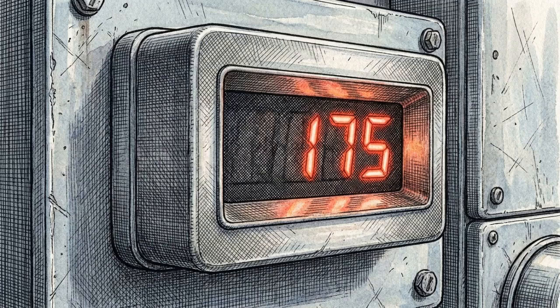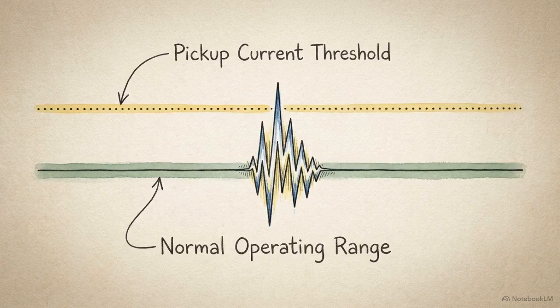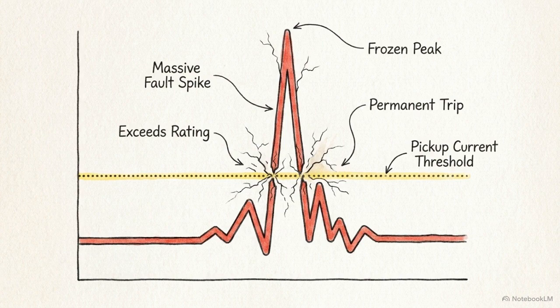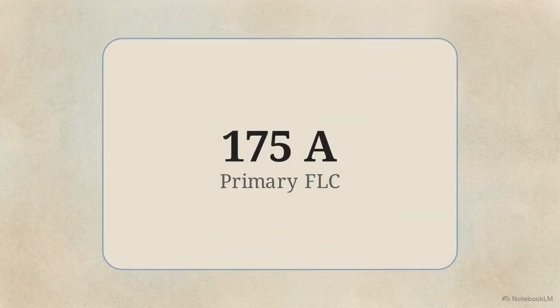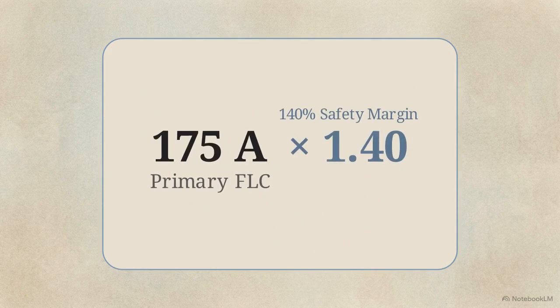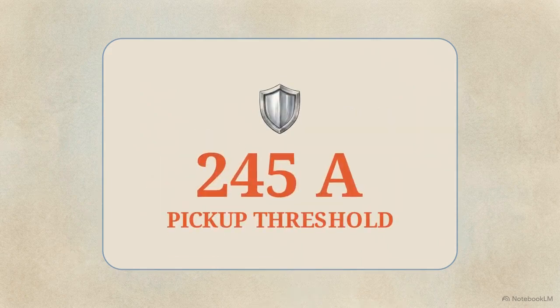A protective relay cannot be set to trigger exactly at 175 amps. The grid naturally fluctuates. We have to calculate a pickup current threshold that sits high enough above the normal operating range to ignore transient surges, but low enough to catch a true fault. For the primary overcurrent setting, we set the pickup at 140% of the full load current. That establishes our true fault threshold at 245 amps.